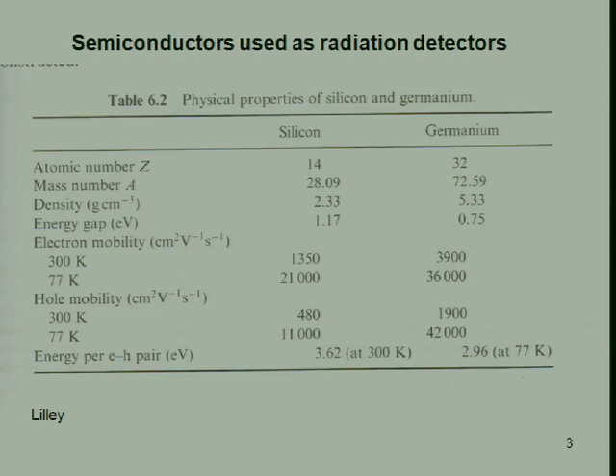And so there's a copper cold rod, cold finger, that's coming out here, touching the back of the germanium right here, coming like this and going down into the liquid nitrogen. The bottom end of that copper rod is sitting in the liquid nitrogen at 77 Kelvin and cooling the germanium to something close to that. And that's required in order to reduce the thermal excitation of electron hole pairs in the germanium so you can get the good energy resolution.